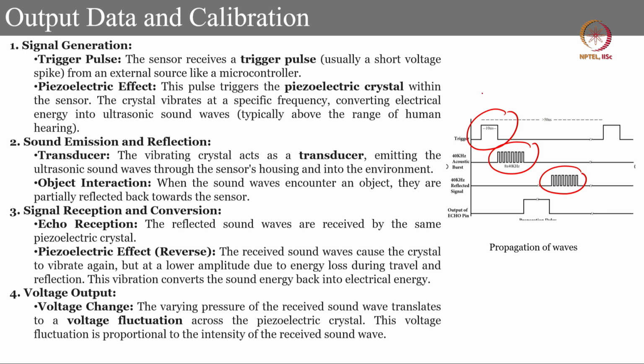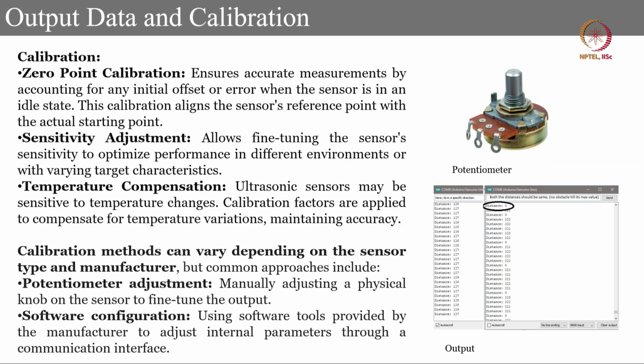So, like this, this is electrical energy, this is acoustic energy. It gets hit to an object and it is returned back, and when it returns back, you can see the burst of signals, and finally you can look at the output. The output voltage change is the varying pressure of the received sound waves translating to a voltage across the piezoelectric material. Now, we also need to calibrate this device. So, what are the different kinds of calibration? Mostly a potentiometer can be used to calibrate it.